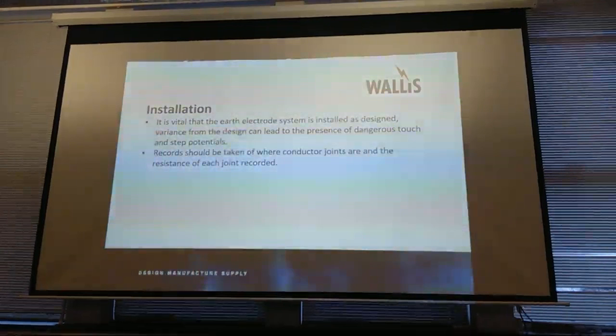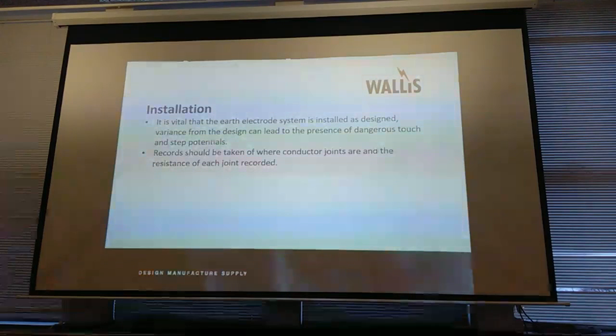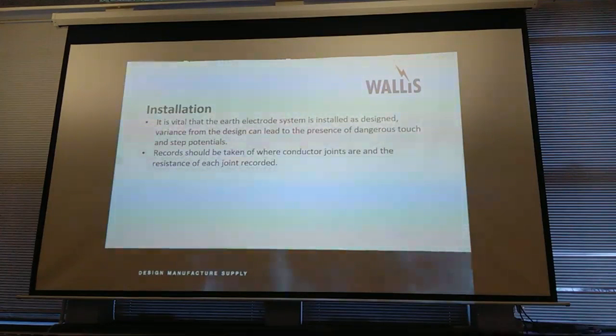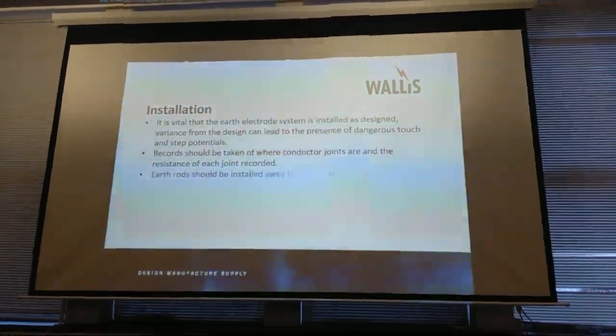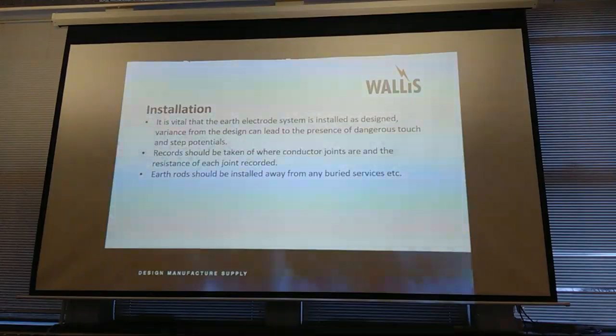Records should be taken of where conductor joints are and the resistance of each joint. Because, damn me, you're going to have how many tons of soil over the top of these once it's covered up, and you're never going to get to them again. If you start getting a fault, or in years to come you start testing and you've got an open joint or an open resistance between one rod and another, then it's a good idea to know where these joints are, because at least you can dig at that point, and you know, 9 times out of 10 it could be the joint and not the copper itself. I think that's fairly self-explanatory.